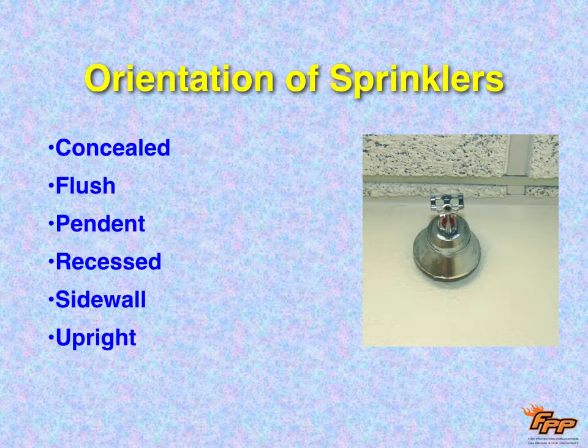But really what we want to know about sprinkler heads is this. We have concealed heads, which are hidden up in the ceiling with a little white cover on them. This is what you're going to see in modern home sprinkler systems. Flush is where it's perfectly flush with the ceiling. Concealed, there's a little cap there and you can see the cap. But the main types are pendant, sidewall, and upright. Pendants hang down, uprights face up. That's the way to remember. Uprights face up, pendants hang down, and then sidewall, they're on the wall and the side of the wall.